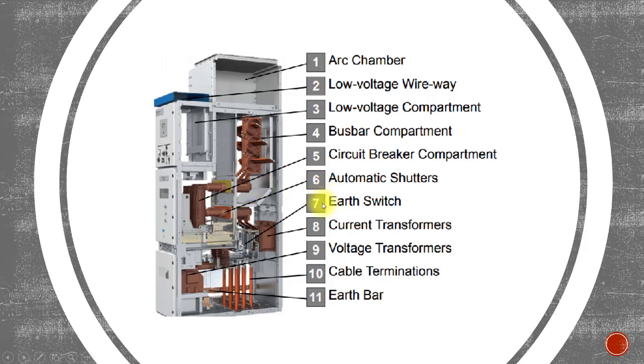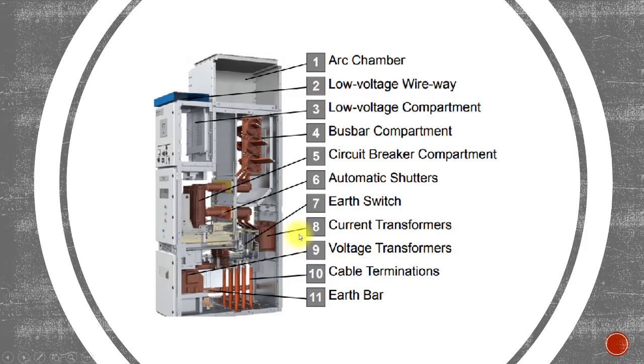Number seven is the earth switch. Normally a three-position earth switch is provided, meaning you can close the isolator, open the isolator, and connect the earth — all with the same device in three positions. In this way, you avoid the need for external grounding of the feeder, and if earth is already closed, the isolator cannot be closed, providing interlock protection.